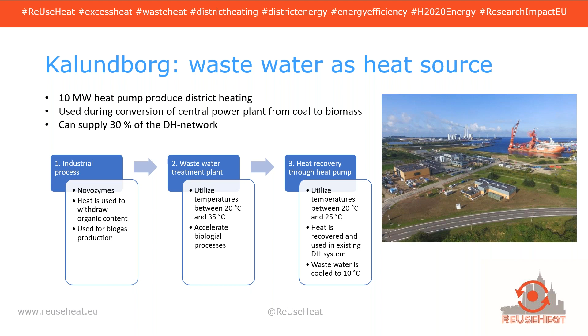Some quick facts about this case: it's a 10 megawatt heat pump, with wastewater as the heat source. The heat pump operates with a COP somewhere between 3.6 and 4.0. Currently there are a lot of operation hours, up to 8,000 hours in the first two years during the downtime of the power plant. After that, they expect to run about 900 hours.